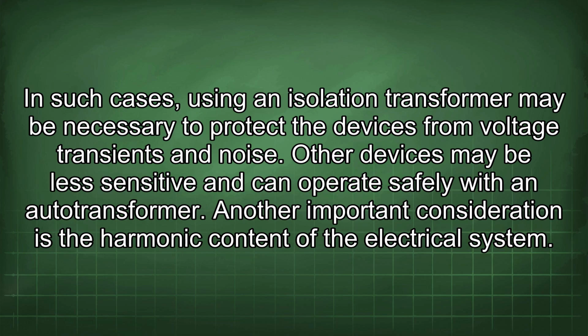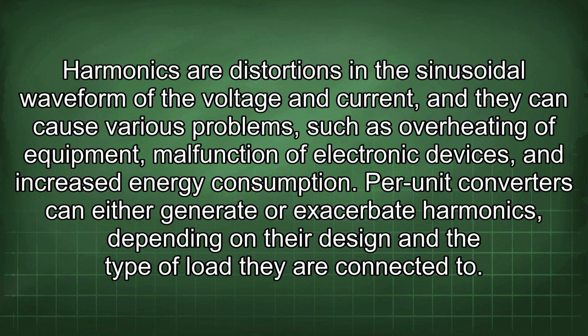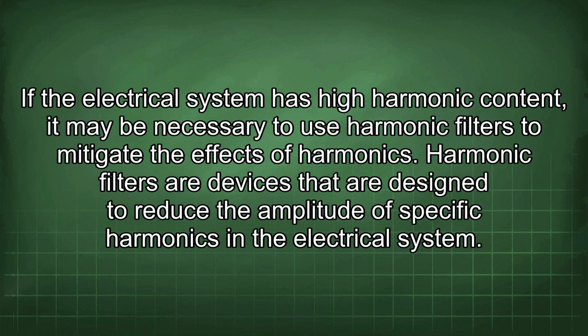Another important consideration is the harmonic content of the electrical system. Harmonics are distortions in the sinusoidal waveform of the voltage and current, and they can cause various problems, such as overheating of equipment, malfunction of electronic devices, and increased energy consumption. Per-unit converters can either generate or exacerbate harmonics depending on their design and the type of load they are connected to.